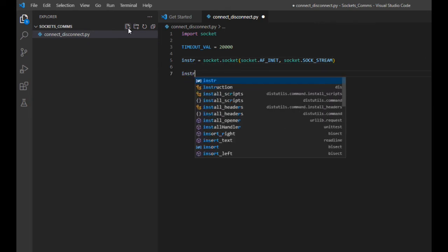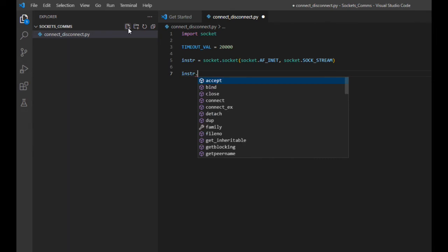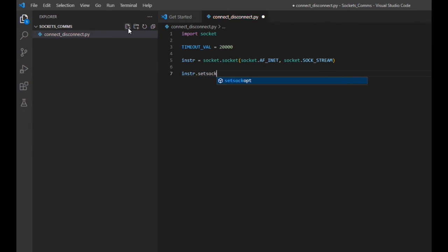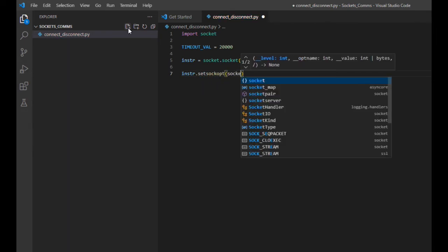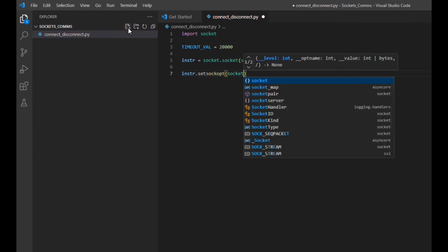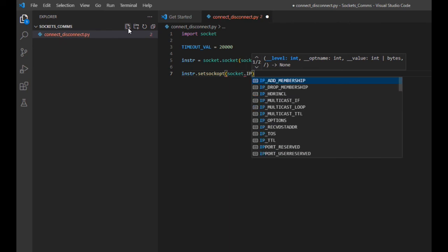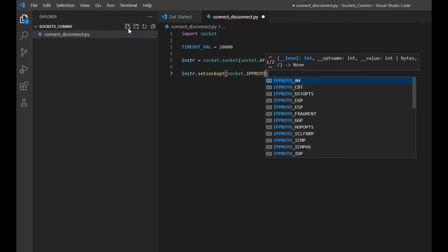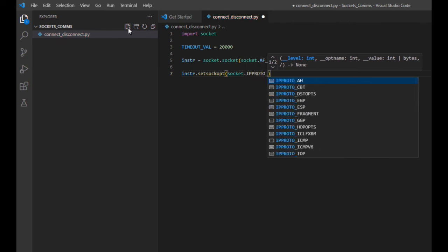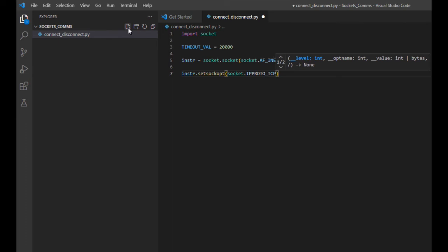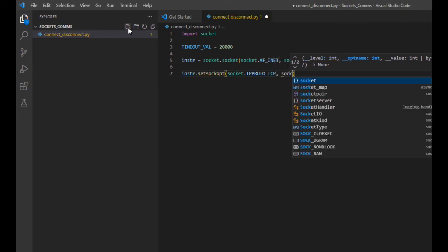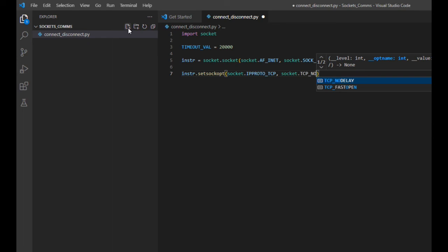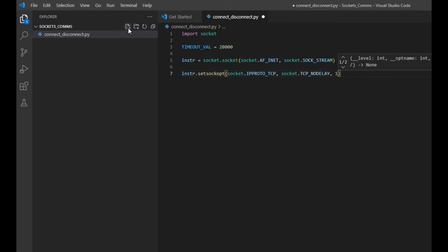The next statement I'm adding here is totally optional, but I want to share it with you for the sake of awareness. In short, we're indicating that we want to disable Nagle's algorithm for this TCP connection. The algorithm is helpful for when dealing with web pages, but it's not as useful here and I've found instances when communicating with instruments where it's proven problematic.